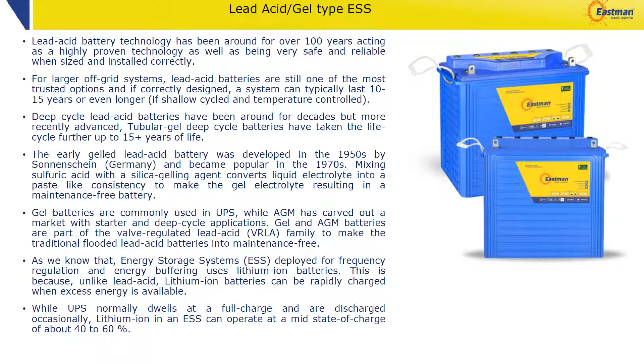Energy storage systems deployed for frequency regulation and energy buffering use lithium ion batteries, because unlike lead acid, lithium batteries can be rapidly charged when excess energy is available. But the advantage of lead gel or lead acid batteries is that they are still commonly used in UPS and most electrical power backup appliances needing economy range products, and even in deep cycle applications with daily discharge up to 50% depth of discharge, or even up to 80% for some off-grid solar projects.